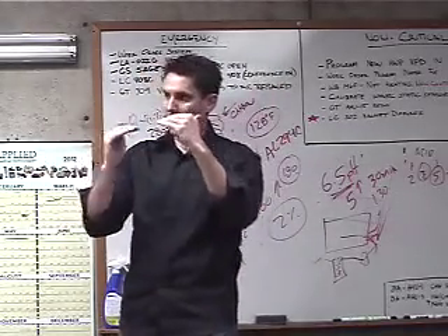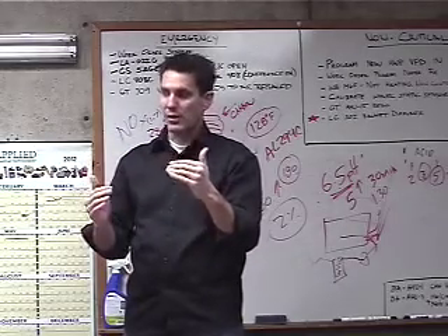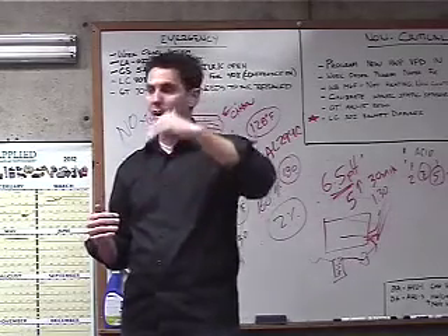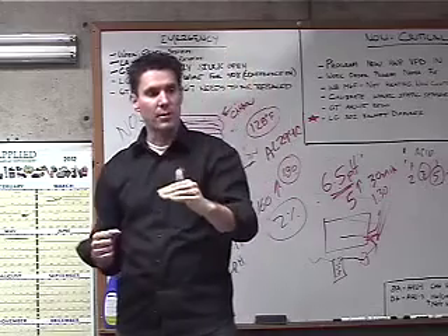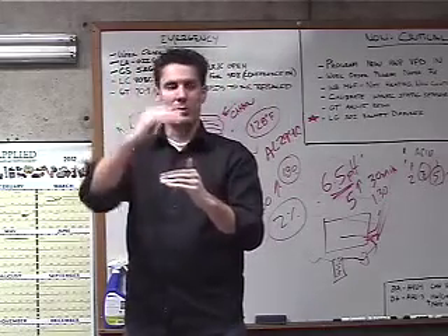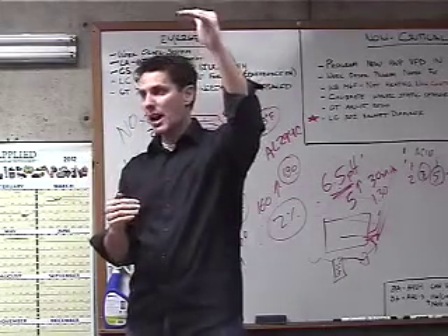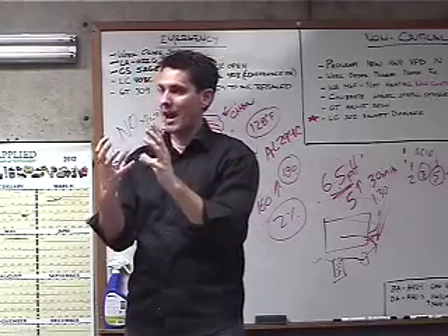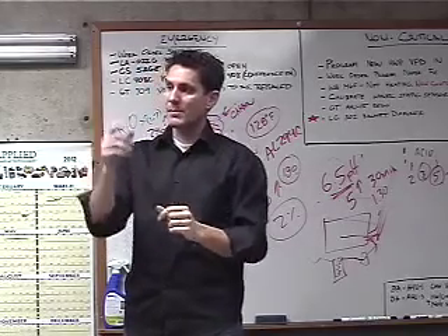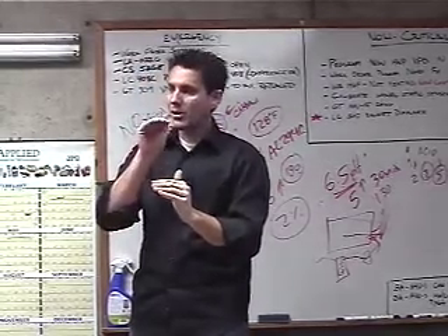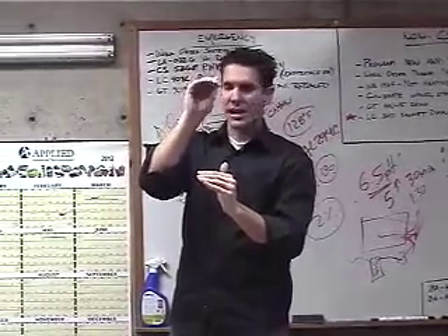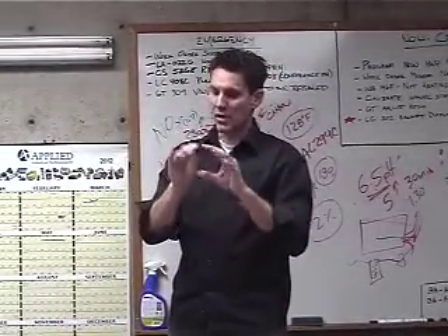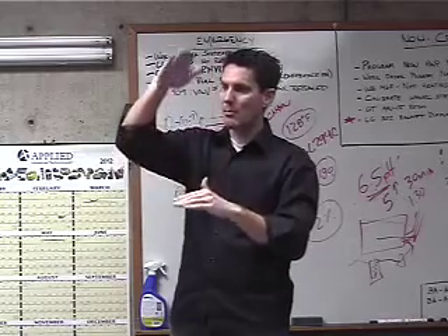So when this thing modulates all the way down, these boilers have a 5-to-1 turn-down ratio. So they'll operate at 100% down to 20% and any infinite point between these two values. So I set it up at high fire, I set it up at low fire so that we have that right combustion. But then this boiler also gives you 8 other points between there, in staged points where you can go in and just make sure, as you tune it up, that each stage through that modulation range.